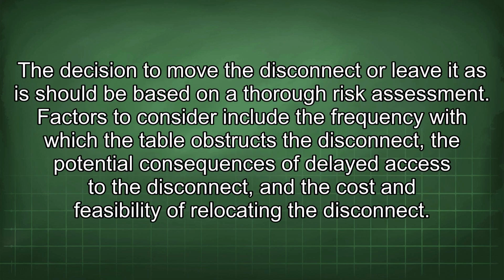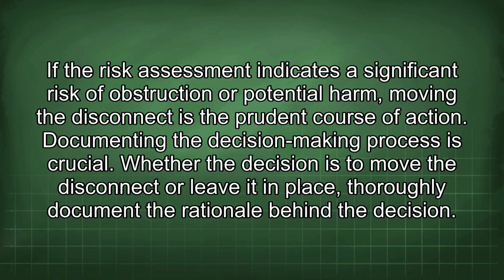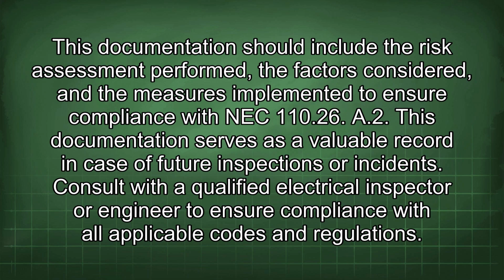The decision to move the disconnect or leave it as is should be based on a thorough risk assessment. Factors to consider include the frequency with which the table obstructs the disconnect, the potential consequences of delayed access to the disconnect, and the cost and feasibility of relocating the disconnect. If the risk assessment indicates a significant risk of obstruction or potential harm, moving the disconnect is a prudent course of action. Documenting the decision-making process is crucial. Whether the decision is to move the disconnect or leave it in place, thoroughly document the rationale behind the decision. This documentation should include the risk assessment performed, the factors considered, and the measures implemented to ensure compliance with NEC 110.26.A2. This documentation serves as a valuable record in case of future inspections or incidents.